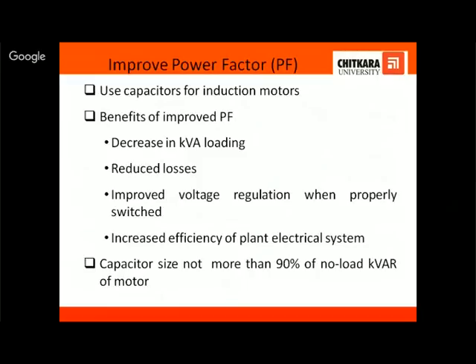Then coming to improving power factors, because the operating power factor of motors is a bit low. When we improve the power factor, it decreases the kVA loading, it reduces the losses, and it improves the voltage regulation and the efficiency of the plant system. But what happens...